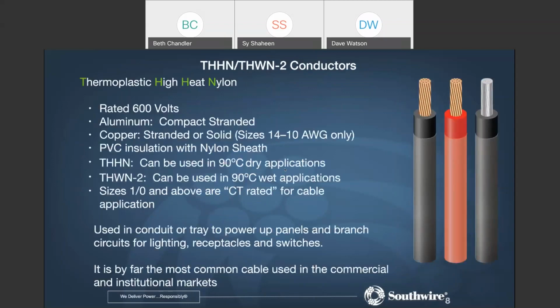Next. So let's go with the THHN, THWN conductors first. These are rated 600 volts. Now, you may have noticed on the last slide that we mentioned 1,000 volts. The thermoplastic products do not have a 1,000 volt rating. It's just 600 volts. You'll see when we go to the crosslink products that they, especially the XHHW, are now rated at 1,000 volts. That's something that occurred within the last 2 or 3 years. This product can be made with either copper or aluminum stranding. If it's copper, it is generally a compressed concentric stranding, or a combination unilay stranding.